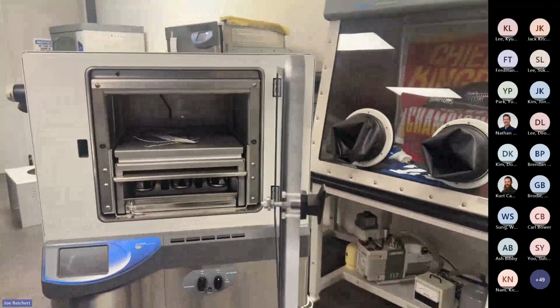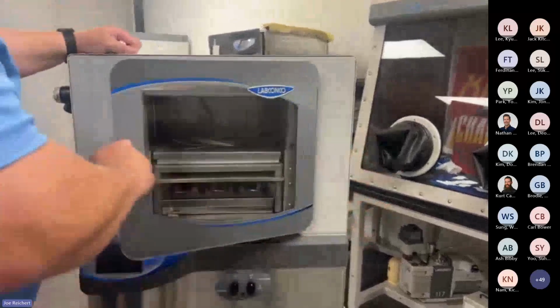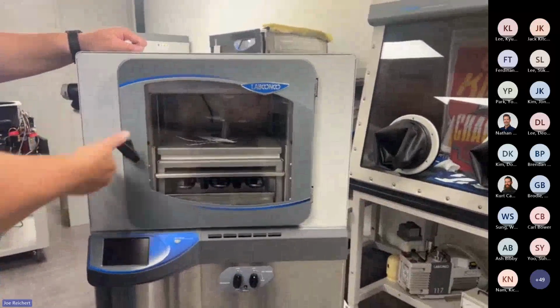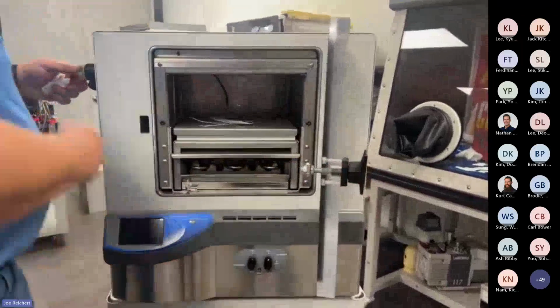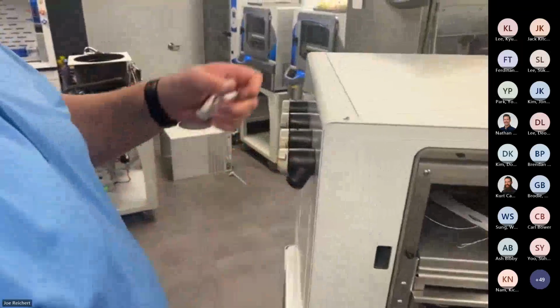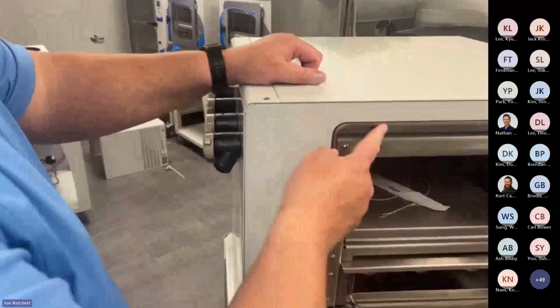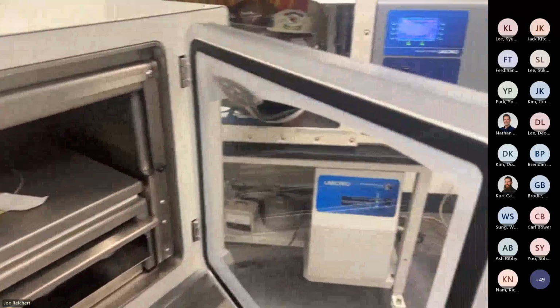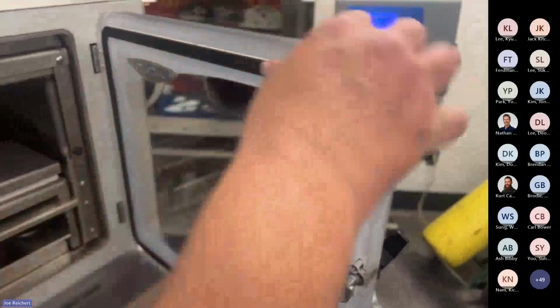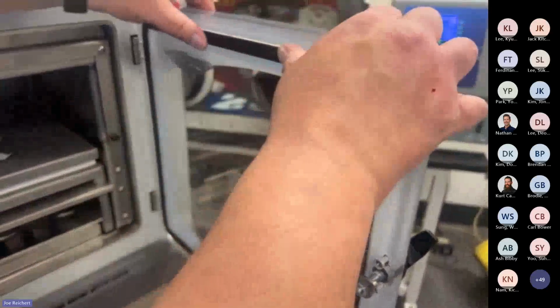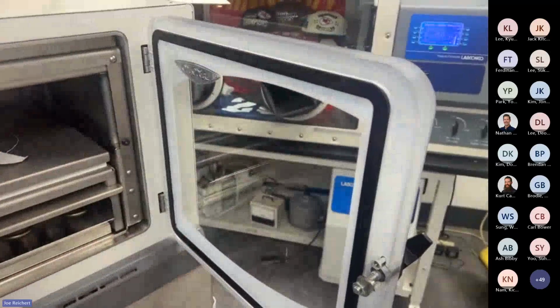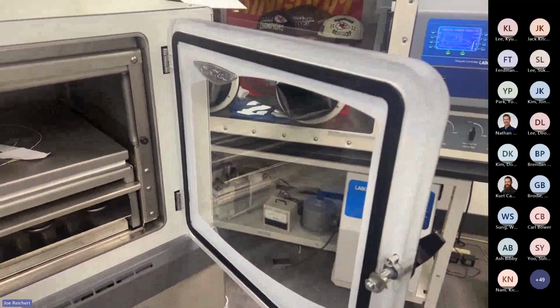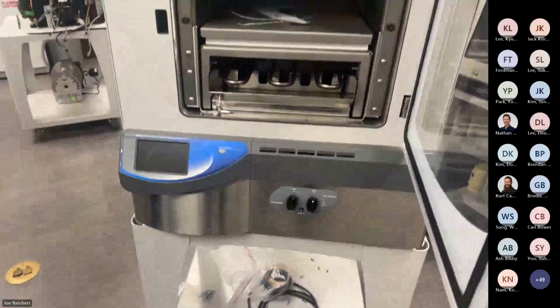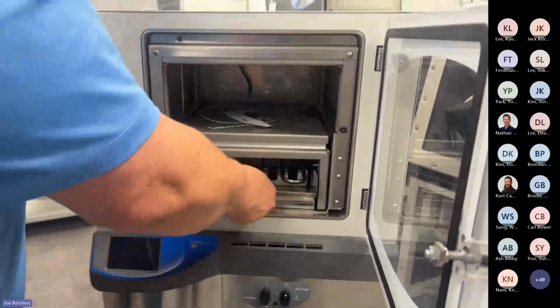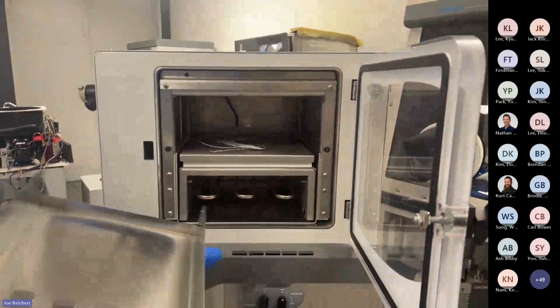If you have an issue where your pump's on and you can't even hold enough vacuum in here to hold the door closed, the pump's on and everything just still opens up, you either have these valves open or your door gasket is not sealing against this metal edge right here. The gasket could have a roll in it. It might be flat over here, but maybe have a hump in the middle or something, keeping it from sealing. But you can also check to make sure the issue is in the chamber just by moving your drip tray and the baffle.